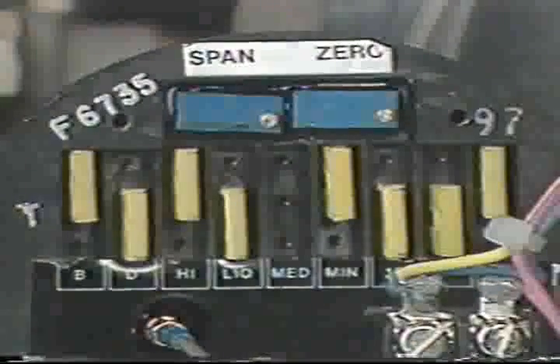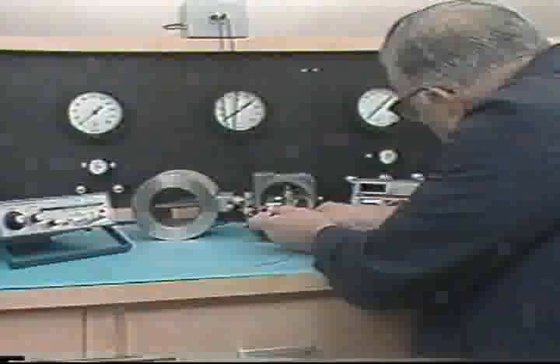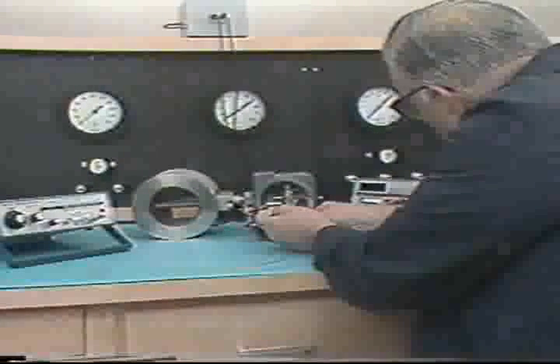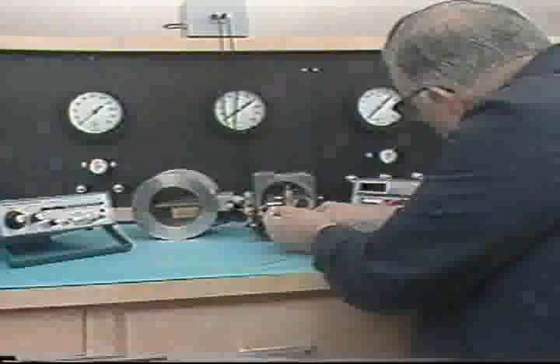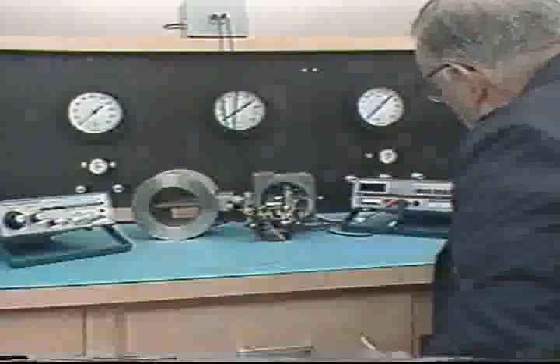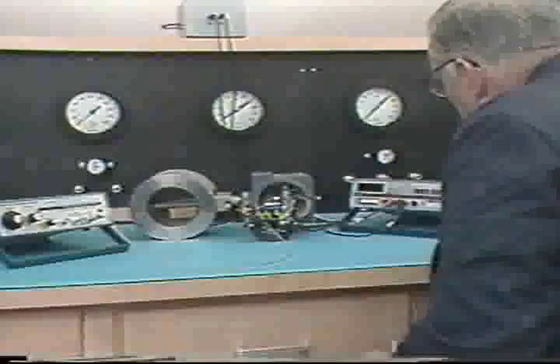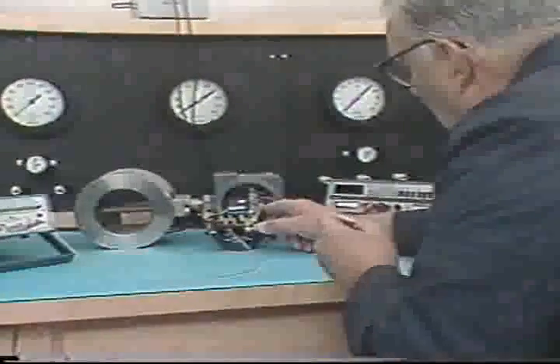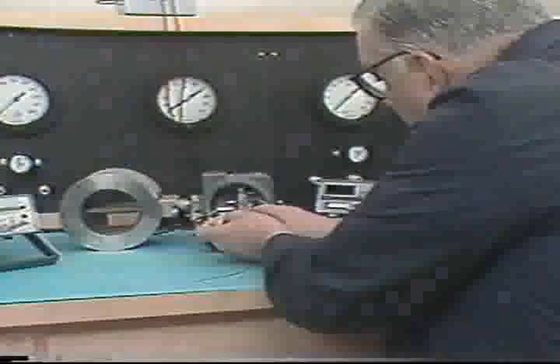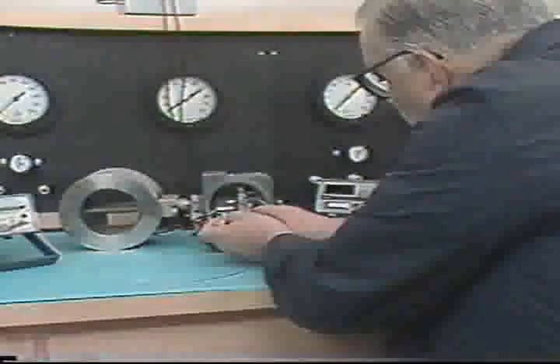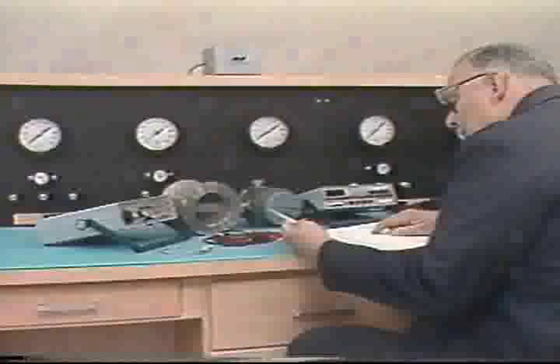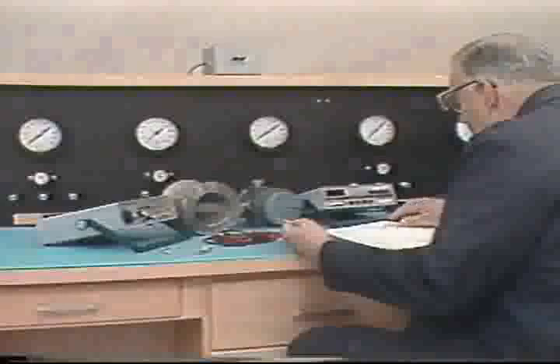Again, since zero and span often interact, the span should be verified to make sure it's properly adjusted. As with other instrument calibrations, the span and zero should be adjusted and readjusted until both are correct. And as in the other instrument calibrations, a 5-point check will verify the instrument's accuracy. We've seen how to calibrate a vortex shedding flow meter. Appropriate input and output standards are chosen to simulate the process signal input and output, and the manufacturer's instructions are used to properly set the input standard so that adjustments can be made to the instrument. Stop the tape now and review what you've seen in this segment.